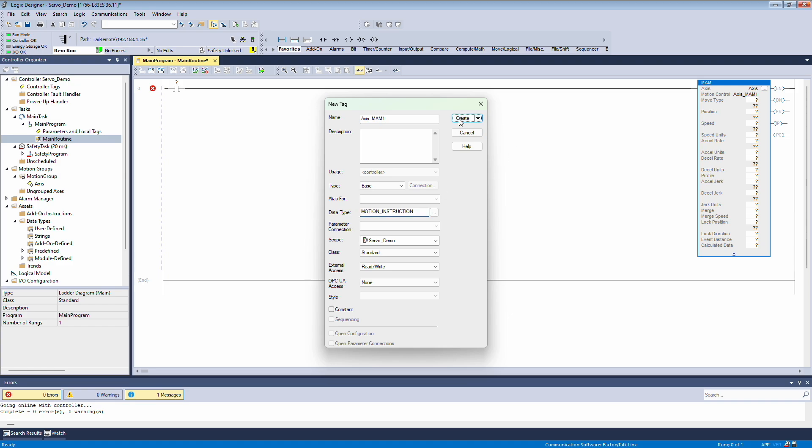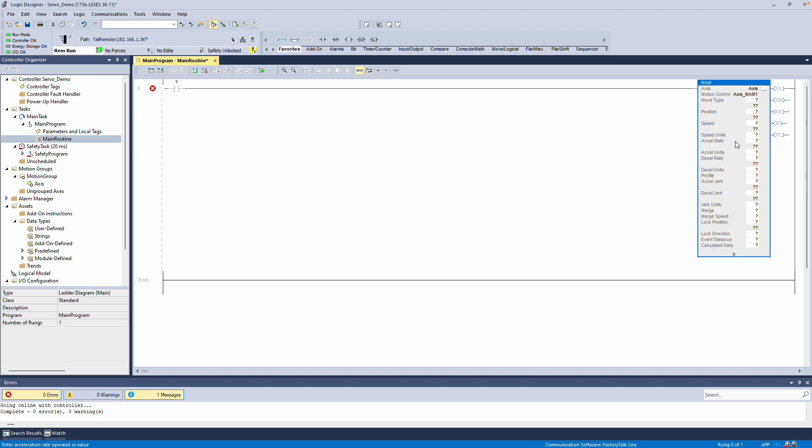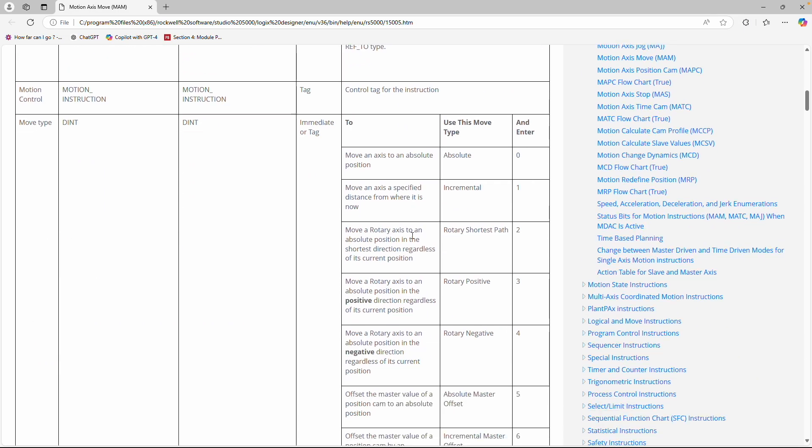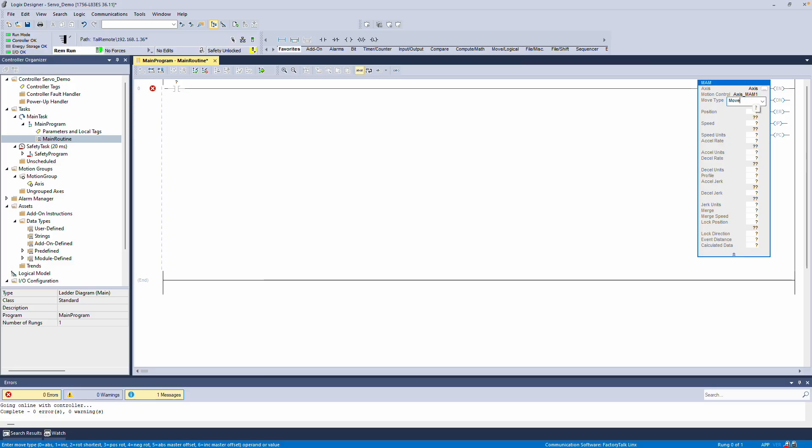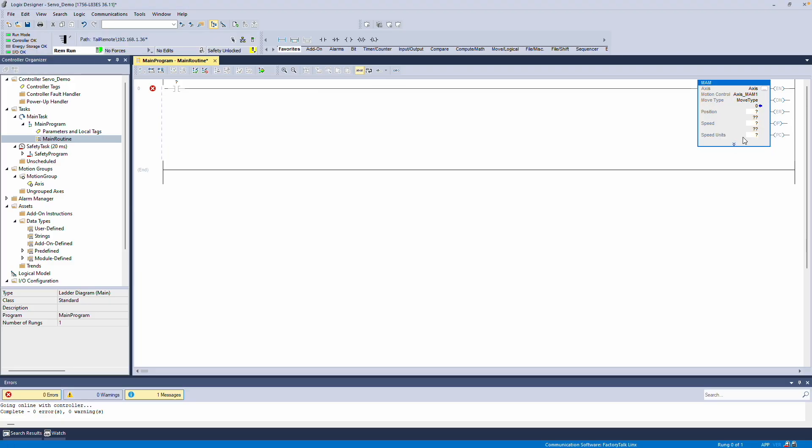Note that each Motion command must have a unique Motion Instruction data element. Now I need to specify the Move type. If you have questions about the Move types, you can check the instruction help for details. The options include Absolute, Incremental, Rotary Short, and others, each represented by a number. We'll use an Absolute move, which is zero. It's a good practice to declare this as a variable, so I'll create a variable called MoveType. We'll do the same for Position, ensuring it is set as a real data type.